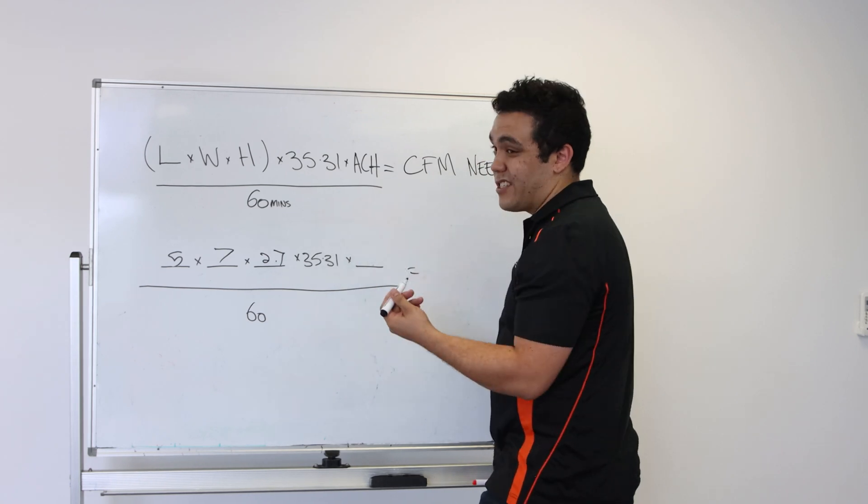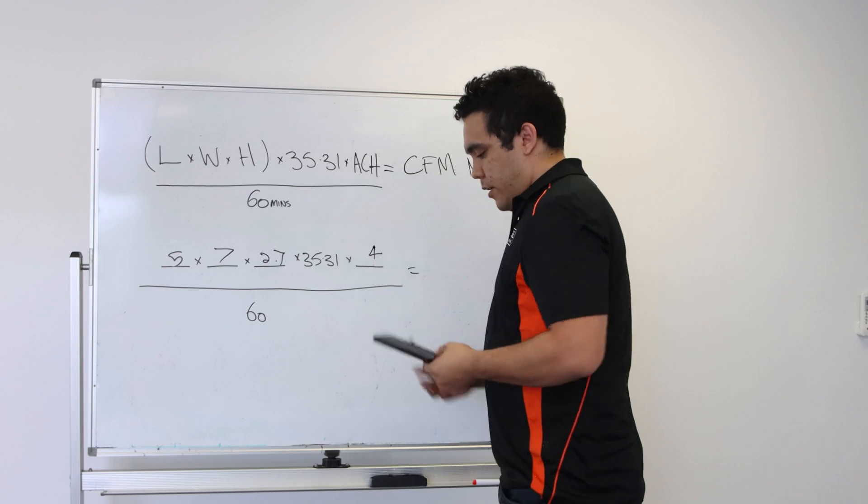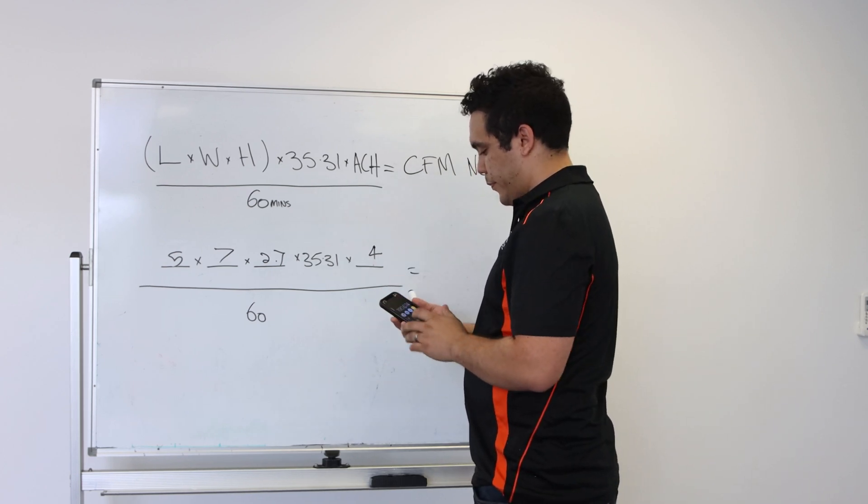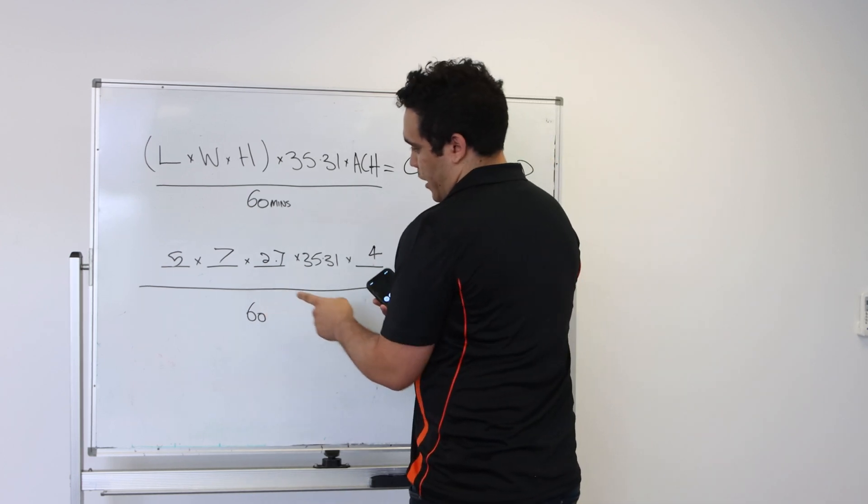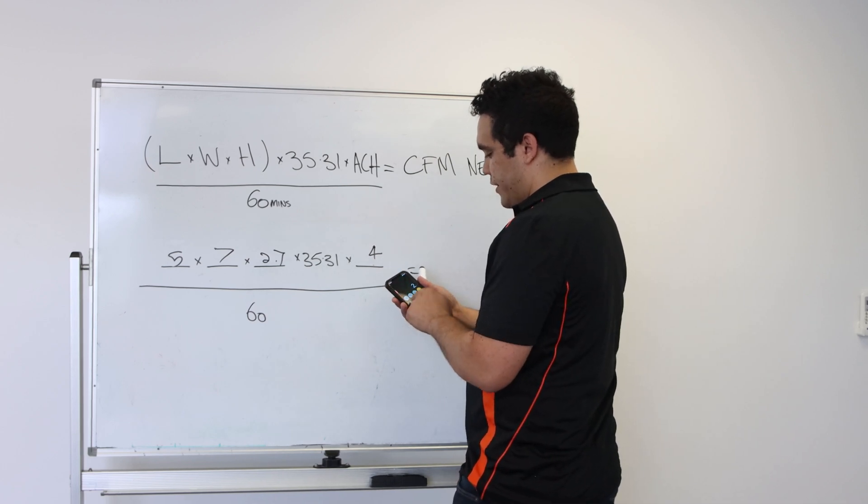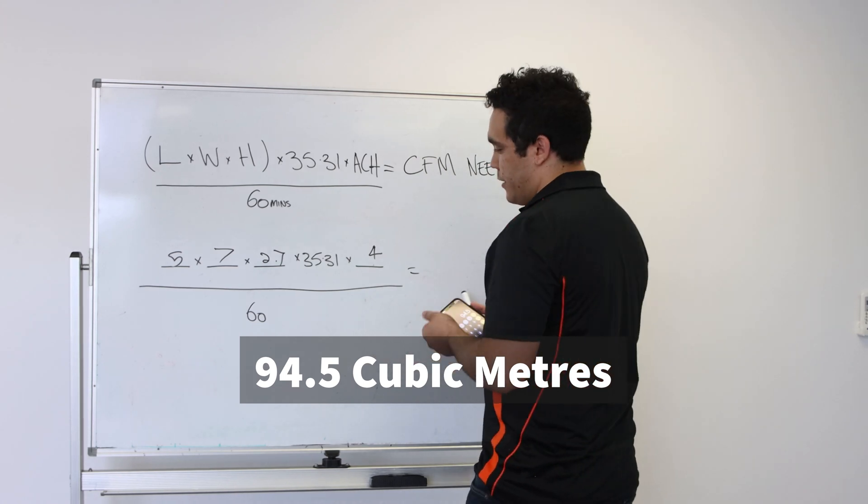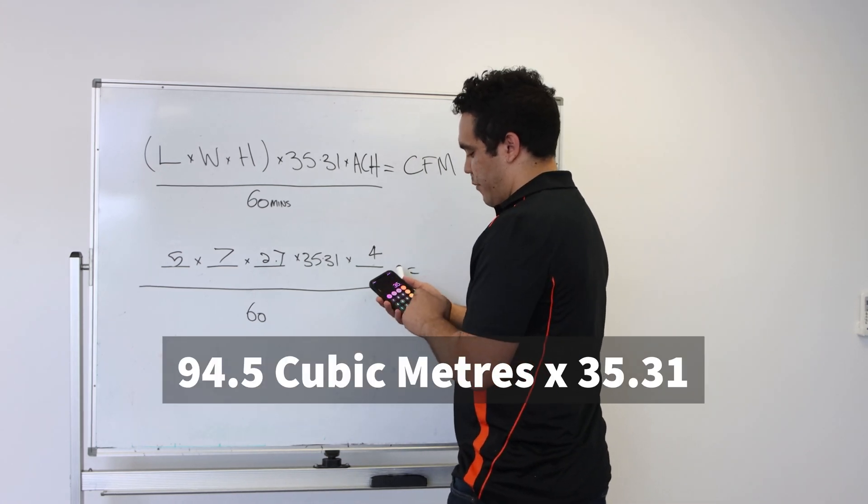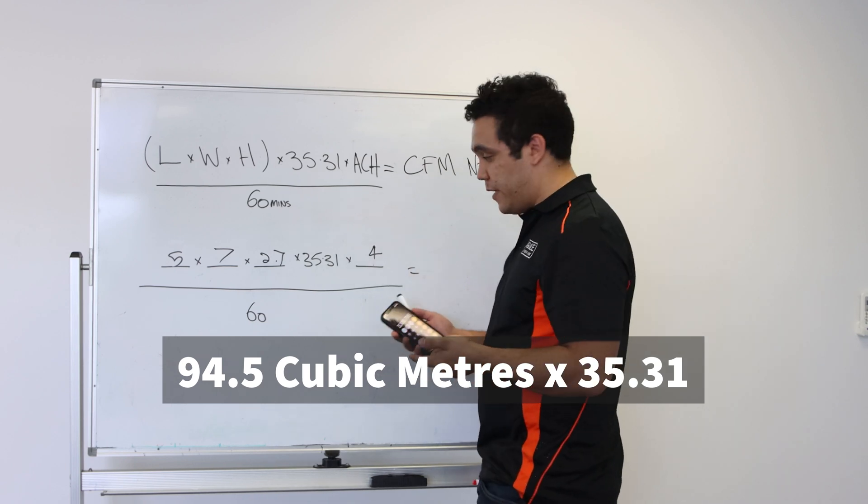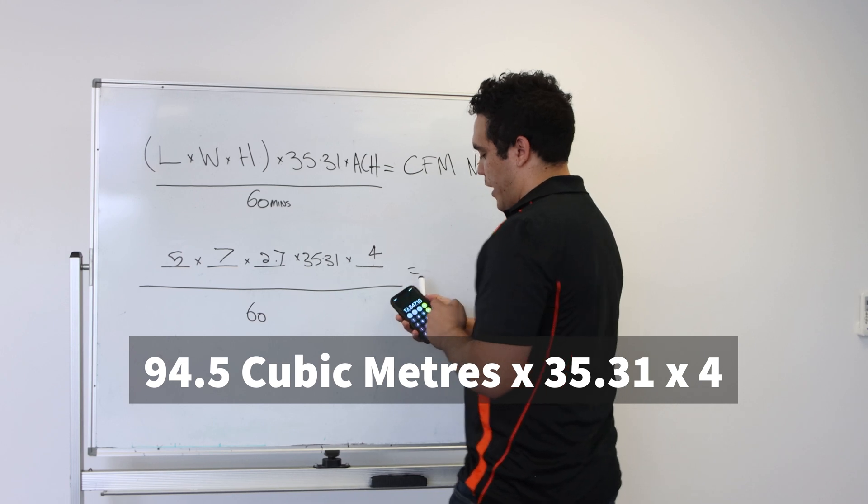So that means it would need at least four air changes per hour. So if I get my calculator out and just calculate this: 5 times 7 times 2.7, which gives us 94.5 cubic meters. And we just times that by 35.31 to get it to cubic feet. And then we multiply that by four air changes per hour.